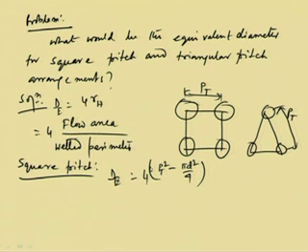So we can understand that if PT square is there, then this is the area of the channel through which it can flow, but these portions are being covered up by the tube. These portions are nothing but 4 into this one quadrant, because this is 90 degree, this is 90 degree. This is one quadrant of the total area of the tube. So 4 multiplied gives you 4 quadrants, that means the area of the tube. So the cross sectional area of the tube is important. If DO is the outer diameter of the tube, then it will be pi d o square by 4.